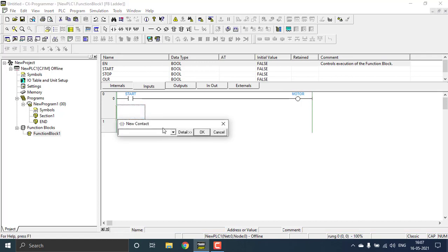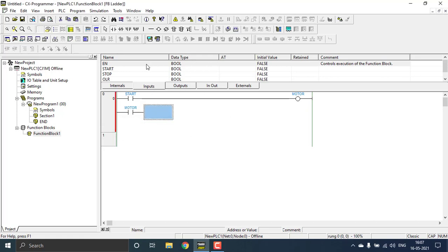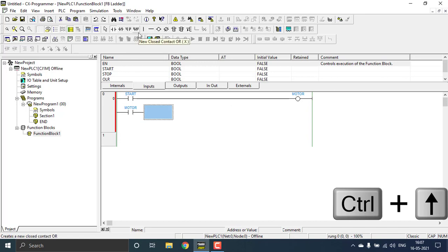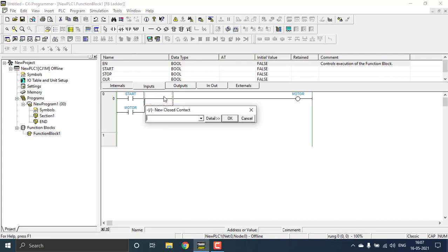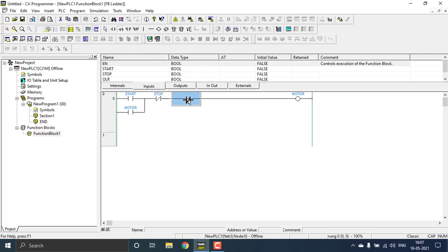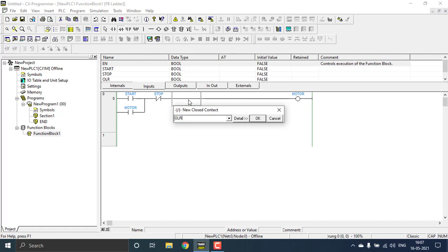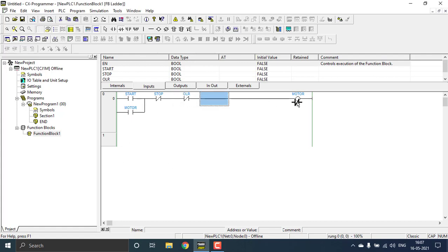Next I'm making the latch for the motor — place a contact here that will be the motor itself, so now it's latched. Then draw it up and add two NC (normally closed) contacts: one for stop and one for the overload protection OLR. So I've completed the ladder logic.